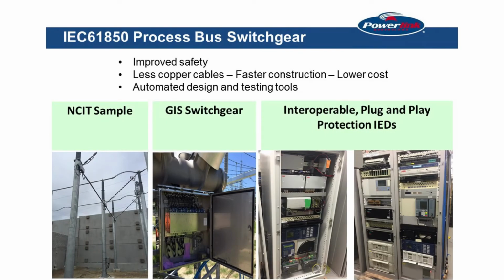Looking at the next stage of IEC 61850 and looking at process bus. Fundamentally, that's allowing us to basically use fibre optic from the measuring devices through to the control room, and then all the way back again to actually trip the switches, which gets us away from a lot of copper in the substations, making it an awful lot easier to install from a cost perspective. So we're looking at how do we leverage off that.